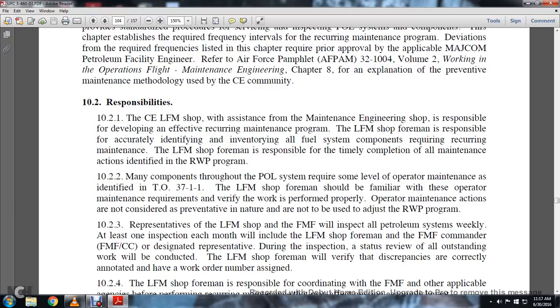All right, responsibilities, 10.2.1. The CE LFM shop, with assistance from the maintenance engineering shop, is responsible for developing an effective recurring maintenance program. The LFM shop foreman is responsible for accurately inventorying all fuel system components requiring maintenance. The LFM shop foreman is responsible for the timely completion of all maintenance actions identified by the recurring work program. Many of the components throughout the POL system may require some level of operator maintenance, identified in TO 37-1-1. The LFM shop foreman should be familiar with the operator maintenance requirements, verifying the work is properly performed. Operator maintenance actions are not considered preventive in nature and are not to be used or adjusted by the recurring work program.